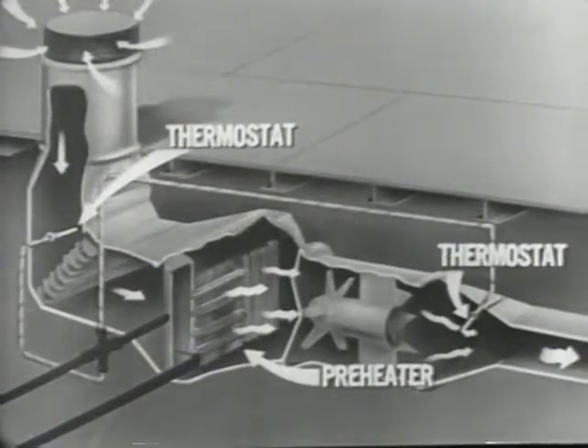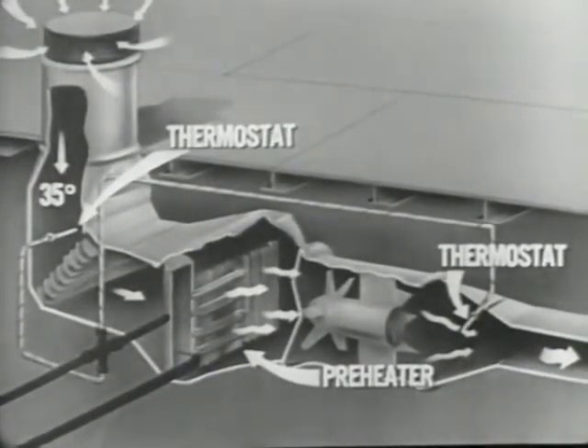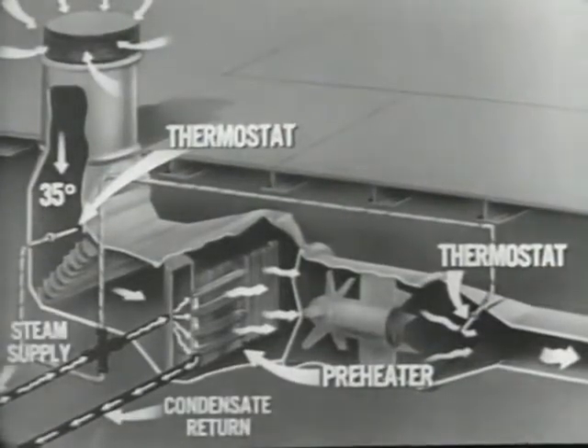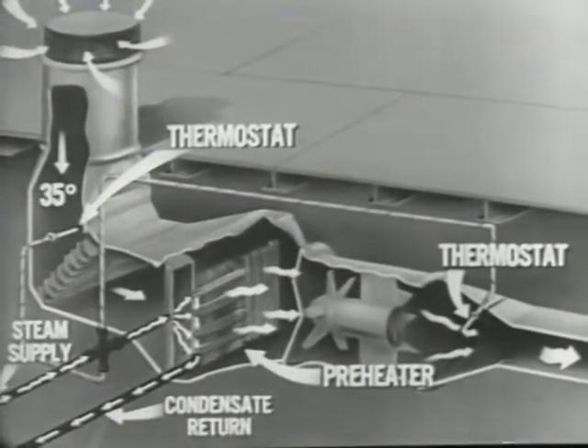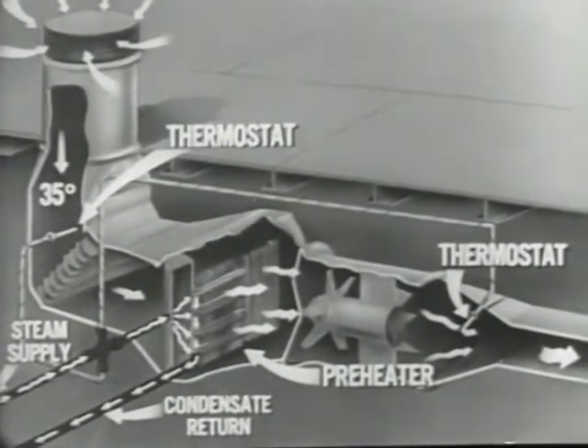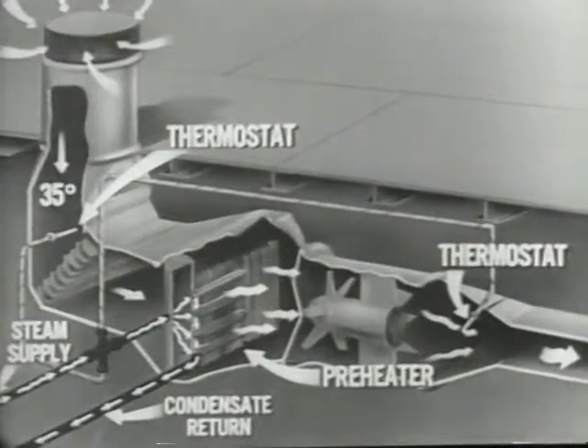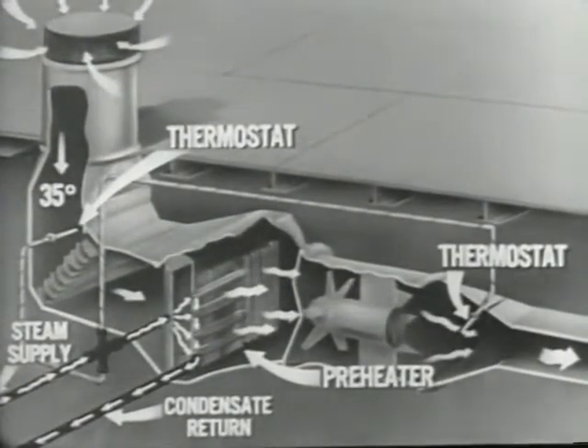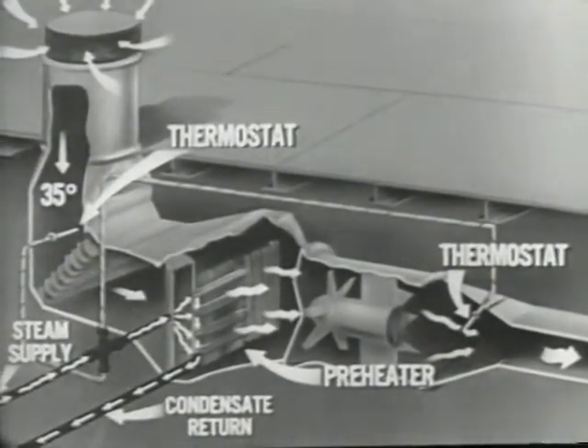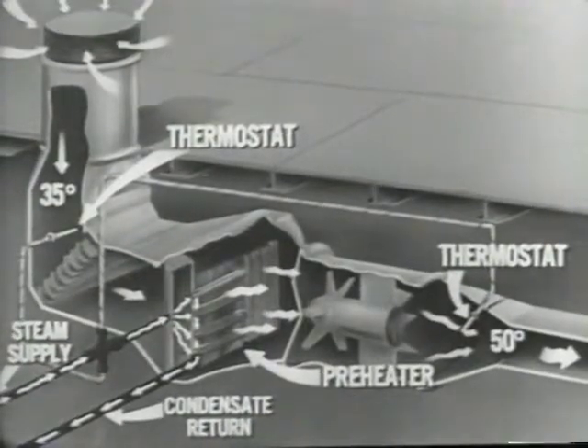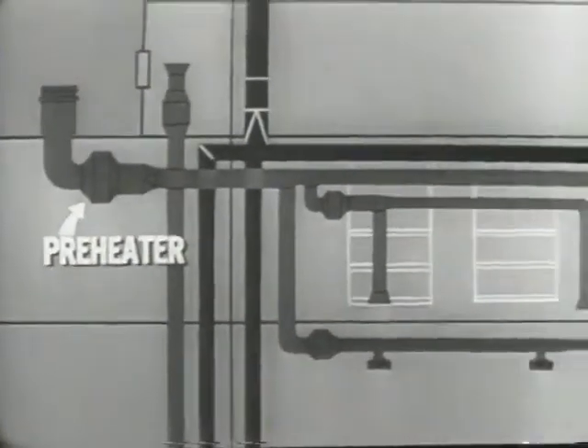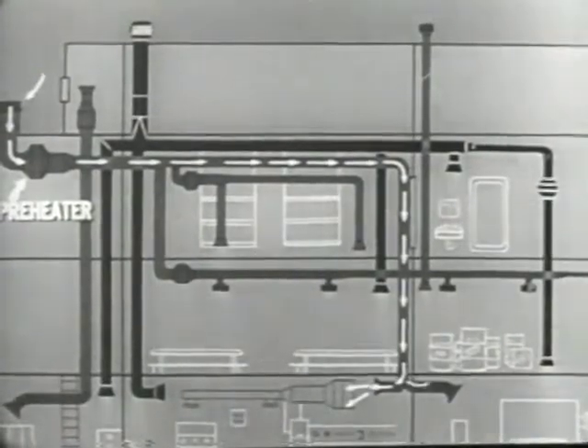When the outside temperature goes down to 35 degrees, the first bulb opens the steam valve, permitting steam to flow into the heater up to 25% of its capacity. This protects the heater against freezing. The second bulb, which controls the remaining 75% of capacity, is set to bring the air temperature up to the desired preheat temperature, usually about 50 degrees Fahrenheit. Air which has been preheated only is directed to inherently warm spaces such as galleys and laundries.